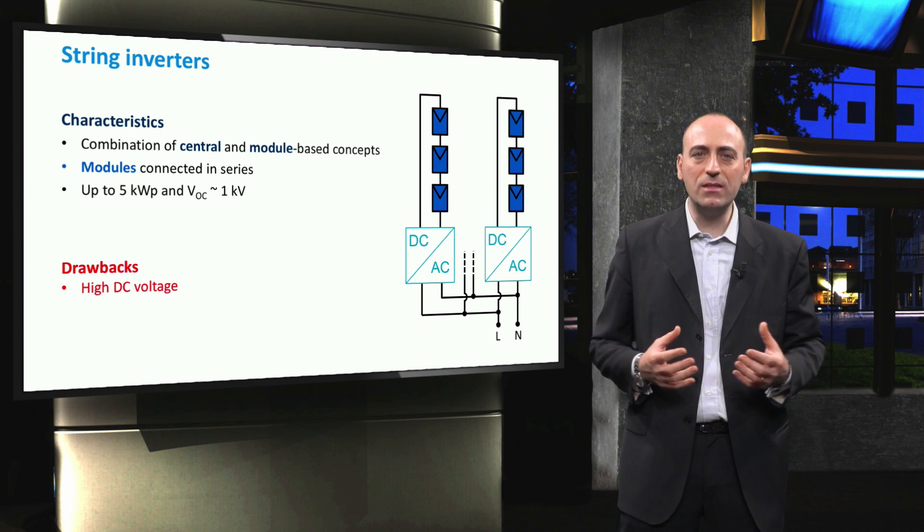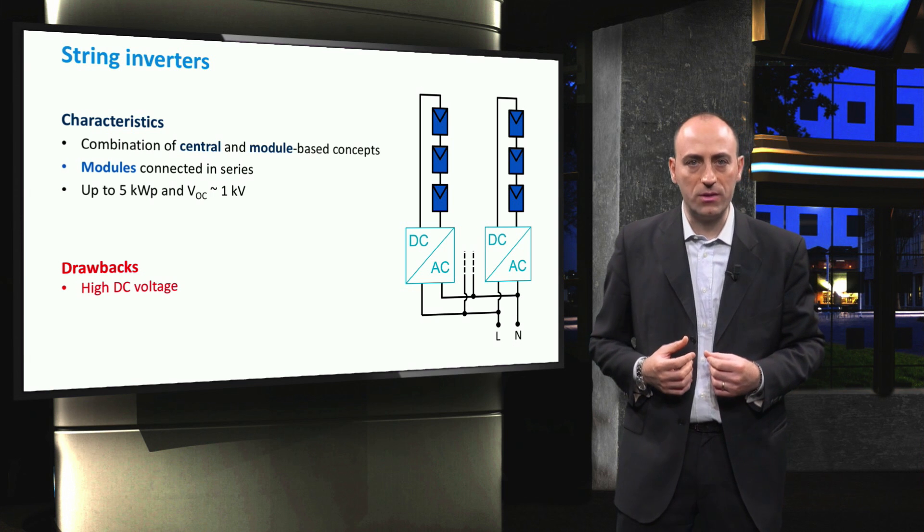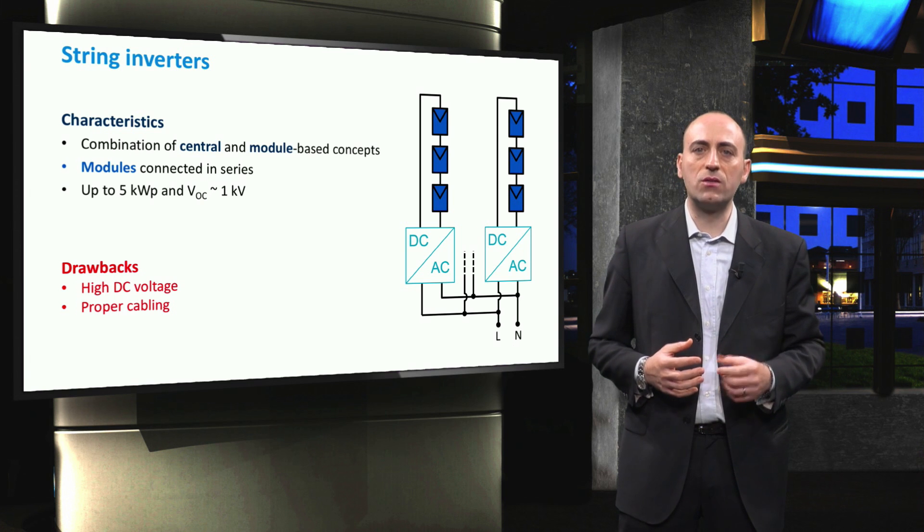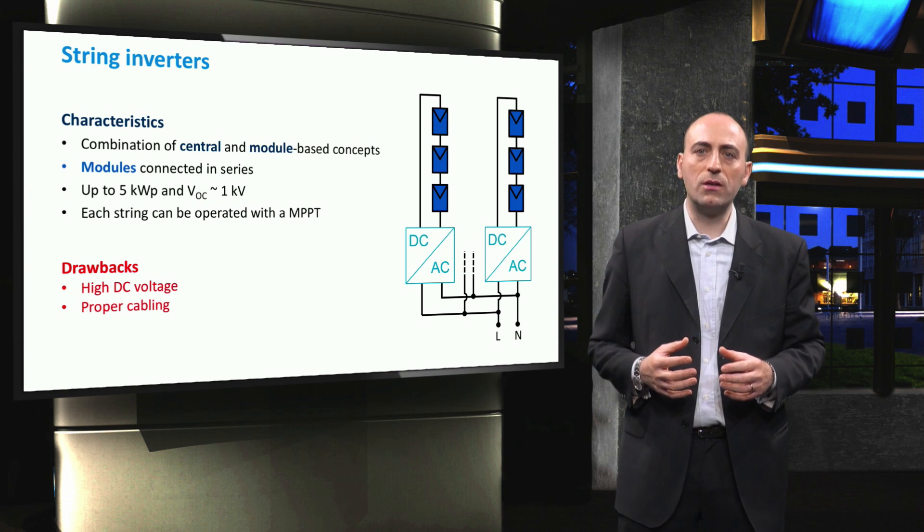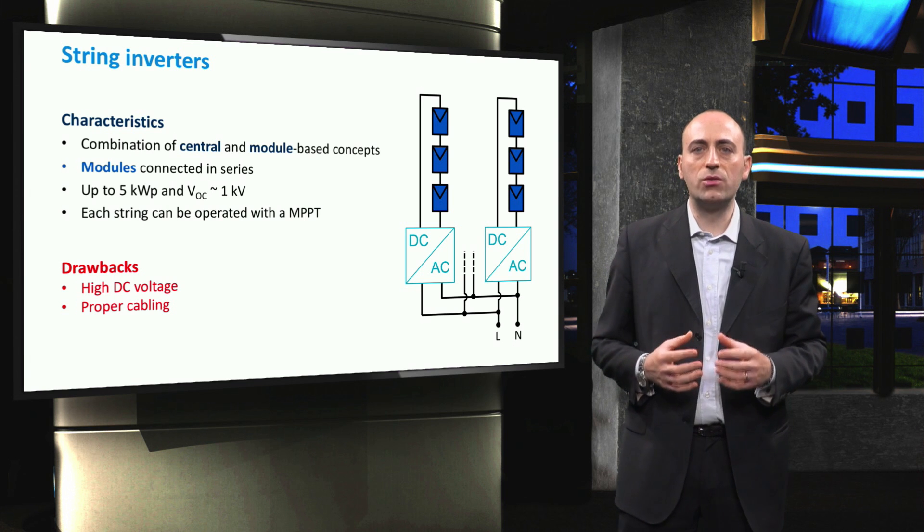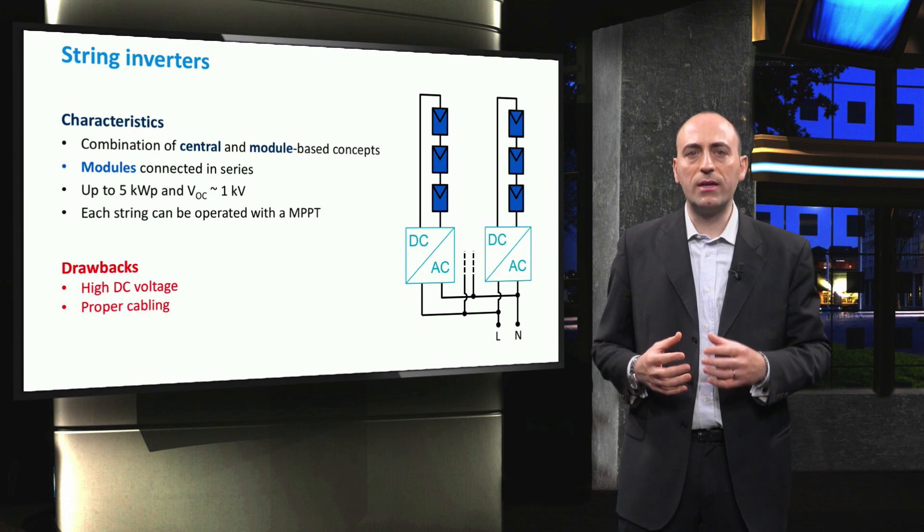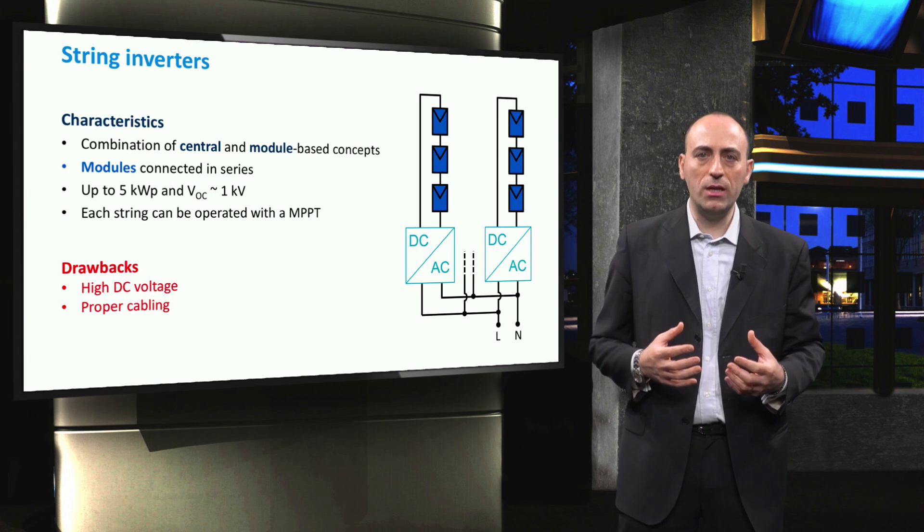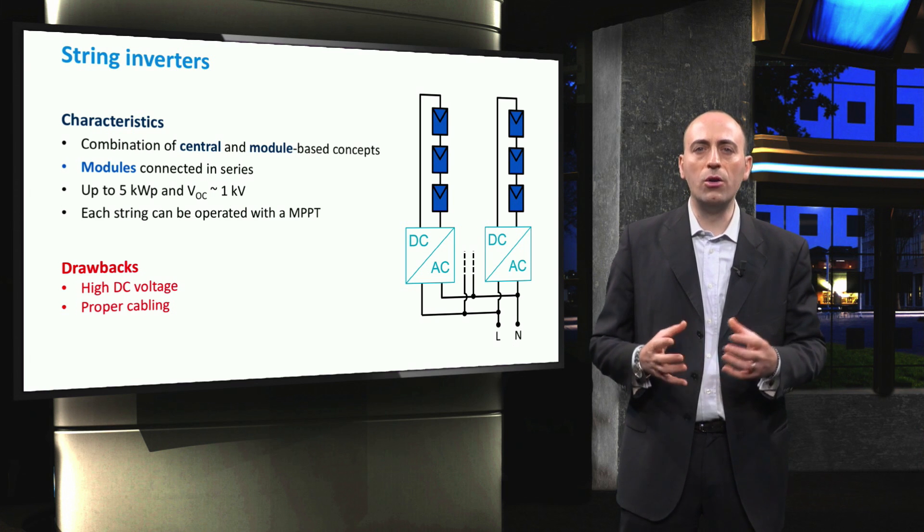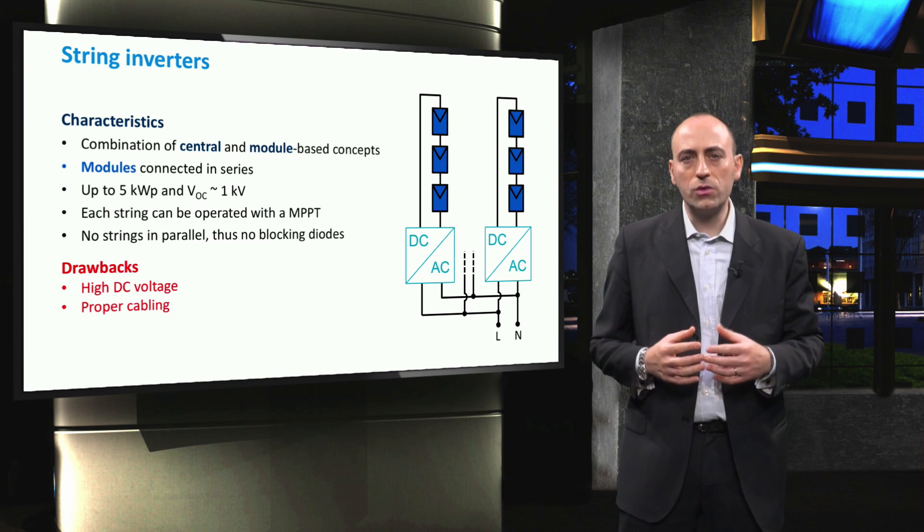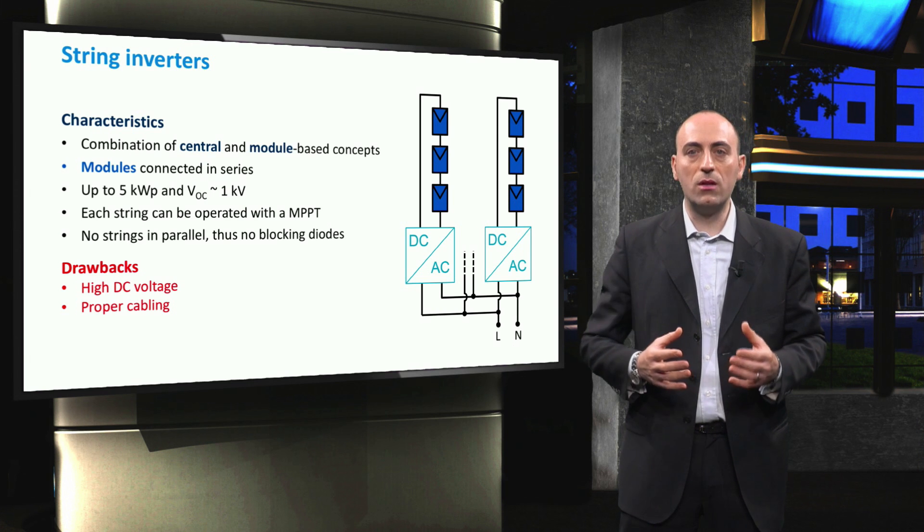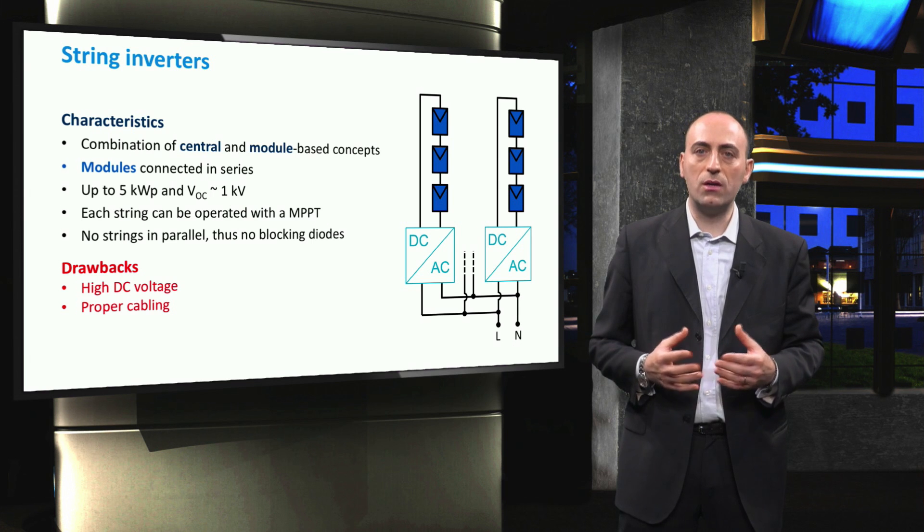The protection of the system also requires special consideration, with emphasis on proper DC cabling. Another important characteristic is that each string has its own MPP tracker, then each string can independently operate at its maximum power point. Thus, partial shading and hotspots will occur only on modules within the string. Also, because no strings are connected in parallel, there is no need for blocking diodes, as in the case of central inverters, and as a consequence, the losses associated with these diodes are eliminated.